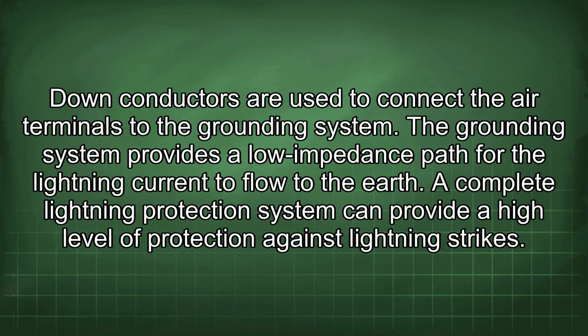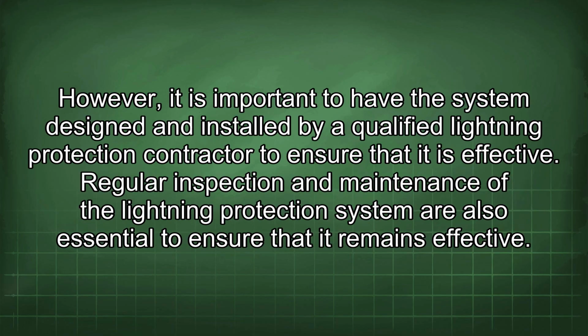Down conductors are used to connect the air terminals to the grounding system. The grounding system provides a low impedance path for the lightning current to flow to the earth. A complete lightning protection system can provide a high level of protection against lightning strikes. However, it is important to have the system designed and installed by a qualified lightning protection contractor to ensure that it is effective.